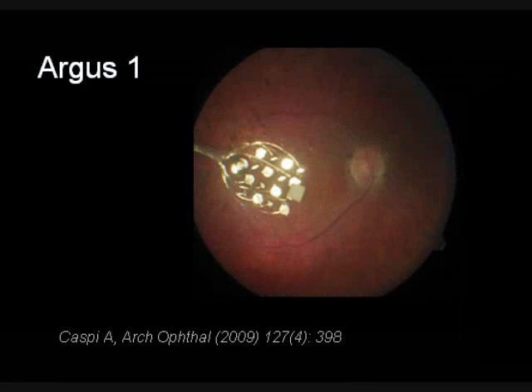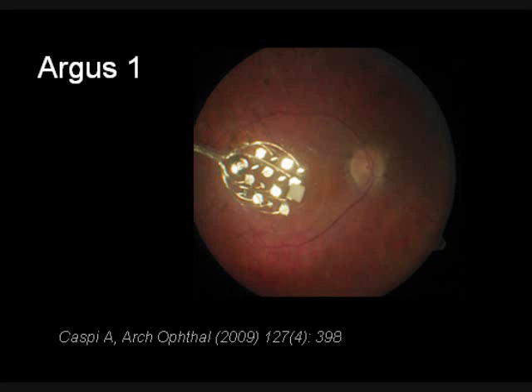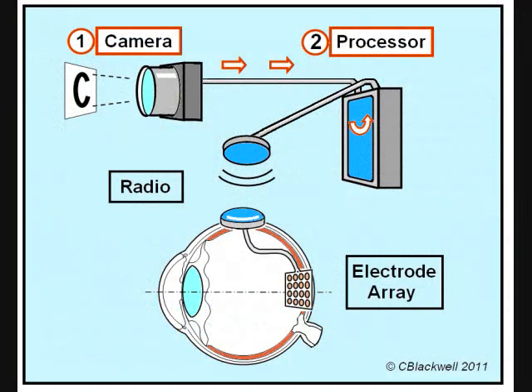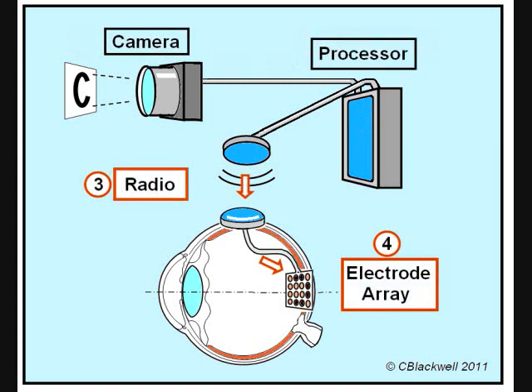The next development is something I didn't think I would see in my lifetime: a functioning artificial retina. There are a number of devices in development. We will look at the device furthest along, developed by Dr. Humayun and his team at USC. The first model, the Argus 1, was implanted in 2002, which successfully functioned at a basic level, and they have since implanted an improved model with more visual detail. In summary, the process starts with an external camera to record an image, which is sent to a processor unit that greatly simplifies it. Then the simplified image is sent wirelessly to a receiver attached to the eye. A grid of electrodes is implanted inside the eye against the retina, and impulses from the electrodes stimulate the remaining ganglion cells, mimicking the nerve impulses from the absent photoreceptors.